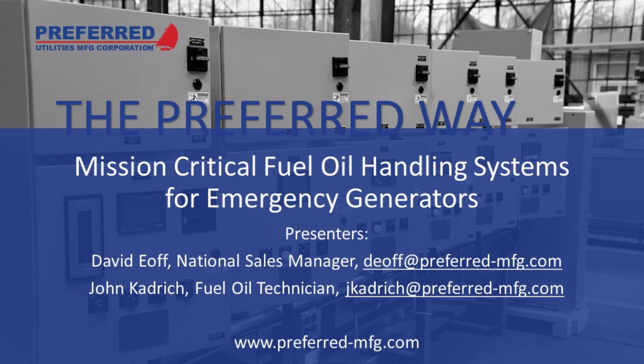But I know in some places that's not supposed to be. Well, with the PLS4, you've got the low, the pump on, the pump off, and the high. And sometimes people put in a backup high. When we see sites like that, we open the bypass on the supply and just fill the tank as far as it'll go and wait for the return pump to kick in. If you designed it right, the return pump should be able to pump out the tank faster than you can put fuel in it. So then you know that your system's working and the chance of a spill is lowered.